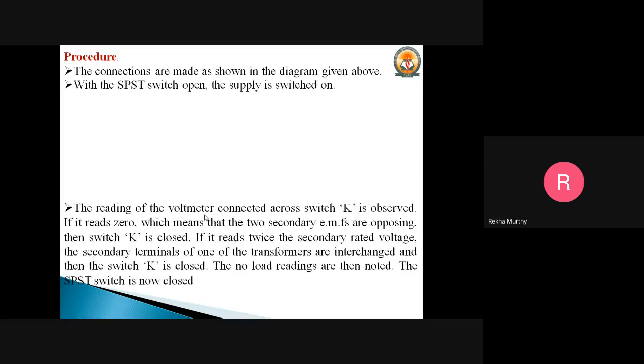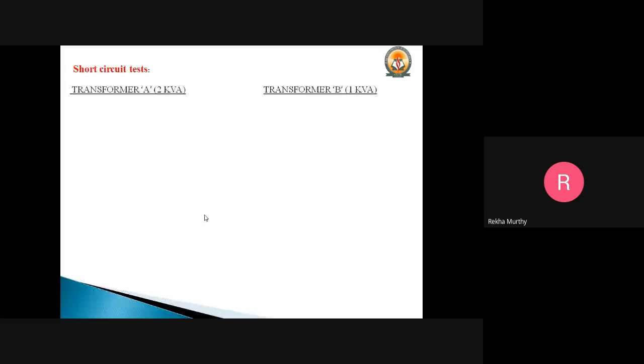What will be the readings which you are going to take from the short circuit test? One transformer will be 2 kVA and another transformer will be 1 kVA. For the 2 kVA, the rated current is 8.7 amperes. This is the same value which you will get as what we did in OC and SC test as the first experiment.